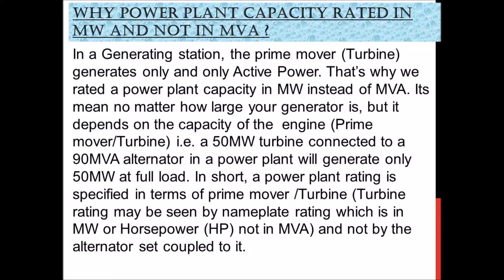It means no matter how large your generator is, it depends on the capacity of the engine, prime mover, or turbine. As an example, a 50 MW turbine connected to a 90 MVA alternator in a power plant will generate only 50 MW at full load.